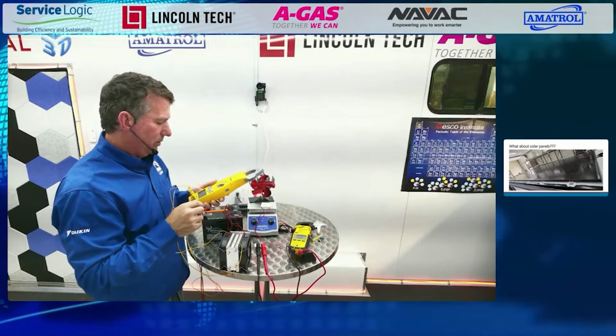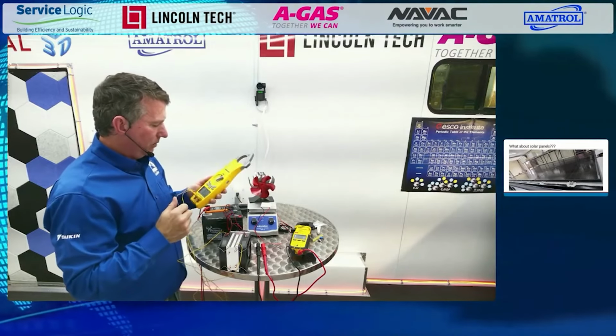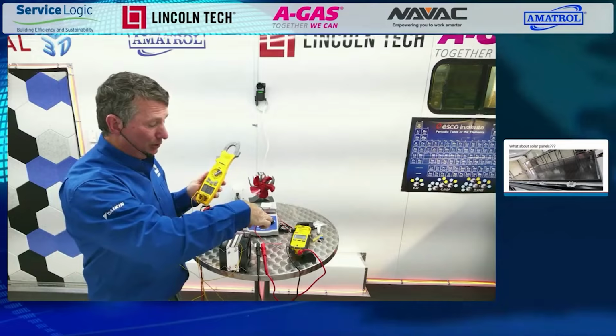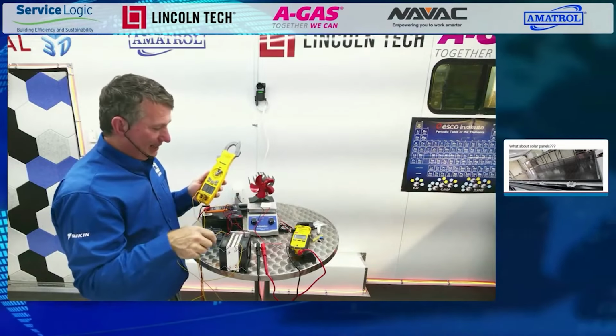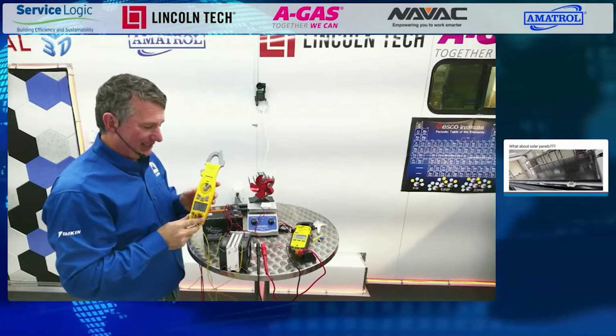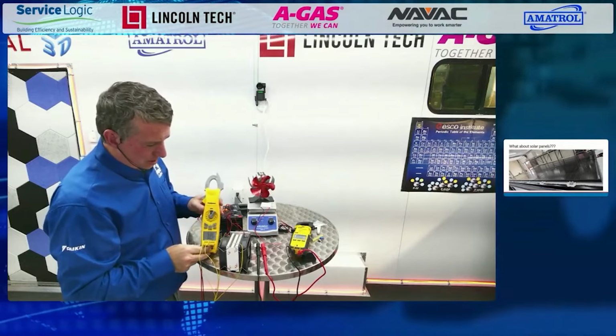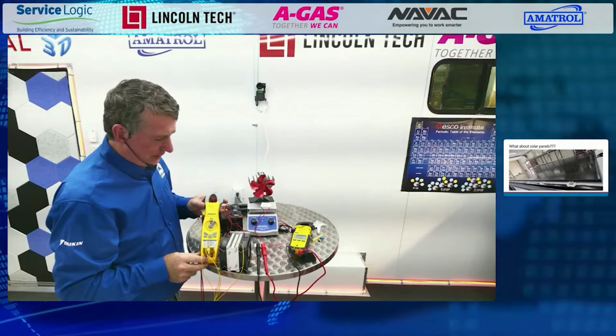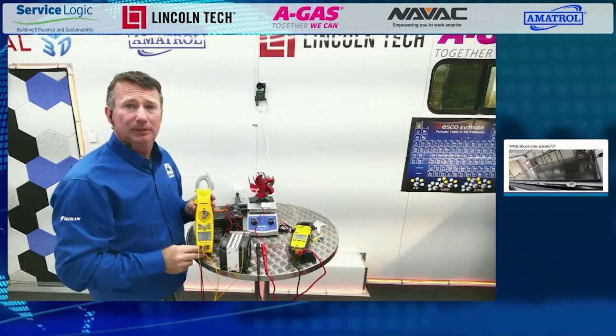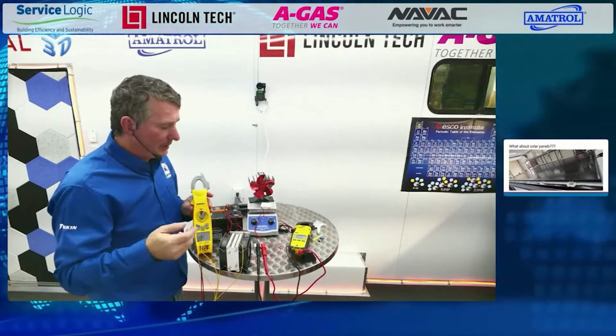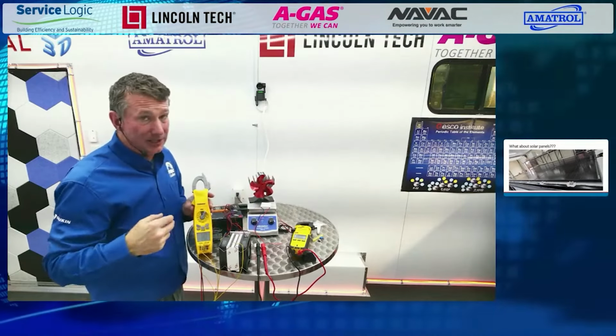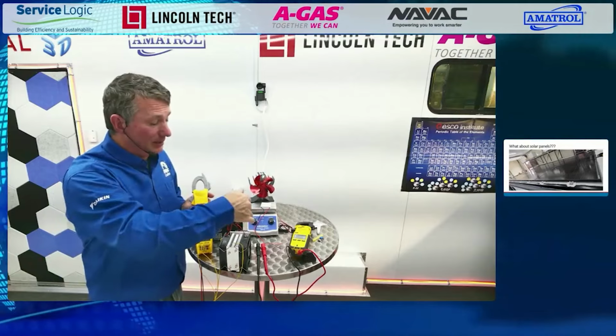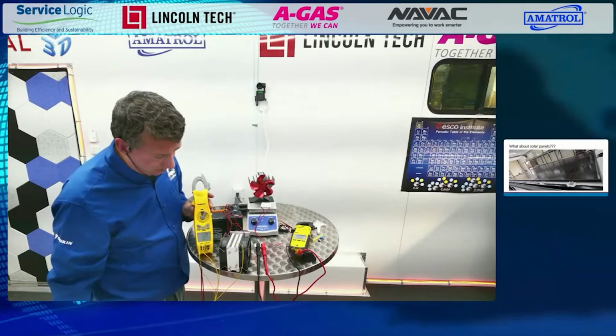There we go. So right now we are running a 52 degree evaporator and an 87 degree condenser, all from electrical flow. Now if I let this run a little bit longer, watch you get down into the 30s, and I am moving air across it, so it's not a stagnant evaporator. This actually is an air over evaporator.